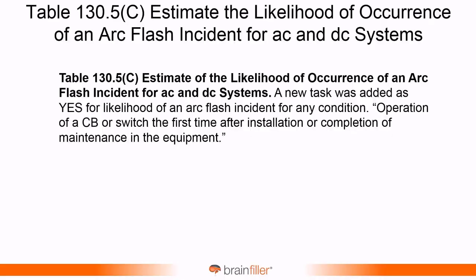Estimate the likelihood of occurrence of an arc flash incident for AC and DC power systems. This is new. This is a new addition. Some people have been talking to me about this, and let me explain what this is about. So we have these tables, and I mentioned the tables. The first sort of version of these tables were introduced in the 2015 edition, and it lists certain tasks, and then it lists, it didn't start out this way, but now it says likelihood of an arc flash, yes or no. And so there's a lot of different tasks in there. And in general, if you have equipment where all the covers are in place, normal operation, and just operating it, it's considered basically not a high likelihood of an arc flash. But there's one in there now that is.